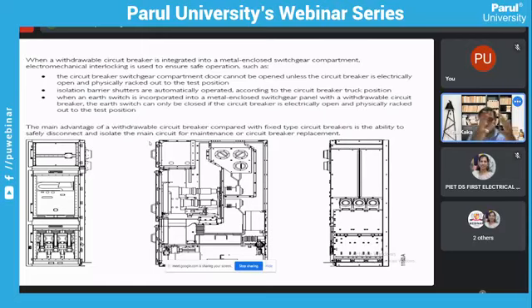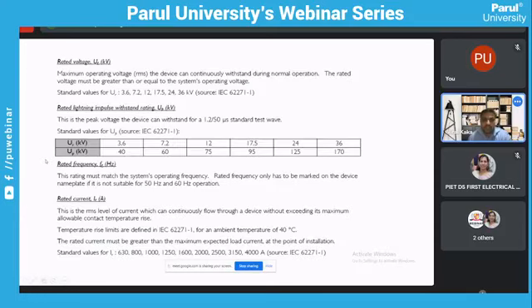So let's say somebody requires the lock or the key for a breaker in isolated position, or we are doing any bus bar maintenance activity. We will rack out all the breakers connected on that particular bus bar, collect the keys of every single individual breaker, and then go to one key exchange box and perform the bus bar earthing operation. So it is ensuring to the operator that every single breaker has been isolated from that particular bus bar, and now it's safe to earth the bus bar. That's how the standard practice is followed in the industry.